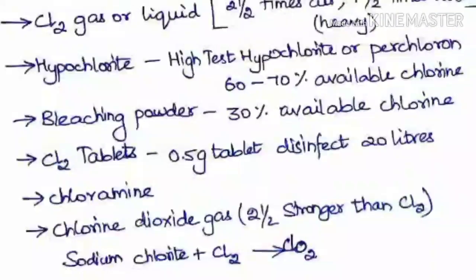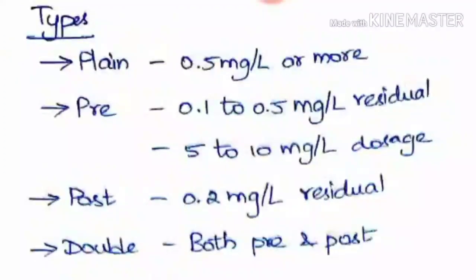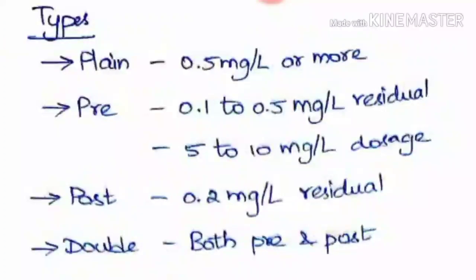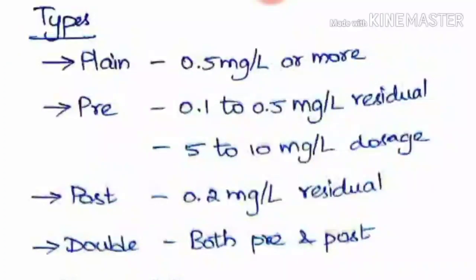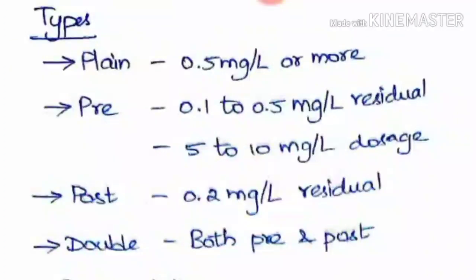The types of chlorination are as follows. The first is plain chlorination, adopted normally with a dosage of 0.5 mg/L or more. The next is pre-chlorination — while chlorination is normally done after filtration, if it is done before filtration or before sedimentation it is called pre-chlorination. This is used when the turbidity of the water is more, with a dosage range of 5 to 10 mg/L.